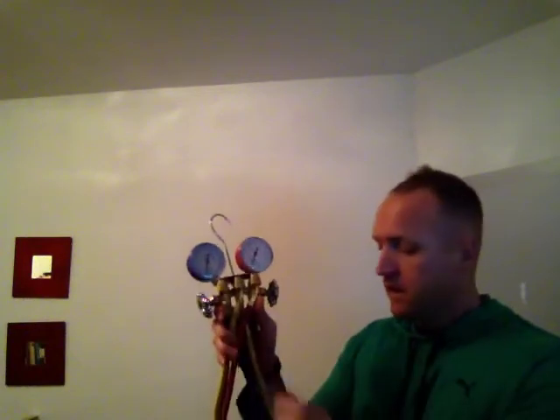Now, through this process, the air that's being brought back from the building actually has to come back in through the air handling ventilation system and pass over that air conditioning coil, where that mechanical refrigerant inside is actually absorbing that heat load from the building. Now, as you can see here, these are a set of manifold refrigerant gauges that I actually use in the field daily when I'm on a service call for air conditioning systems. You have your blue gauge, your blue hose for your low side, you have your red gauge, and your red hose for your high side.